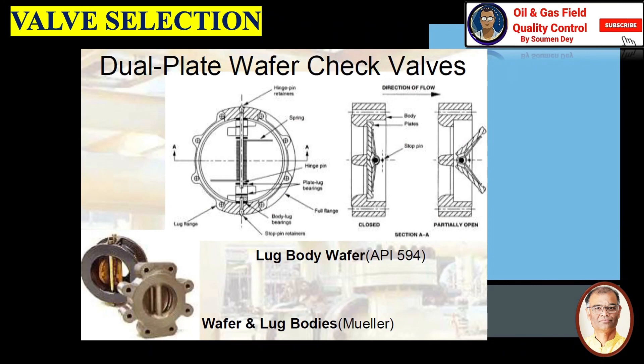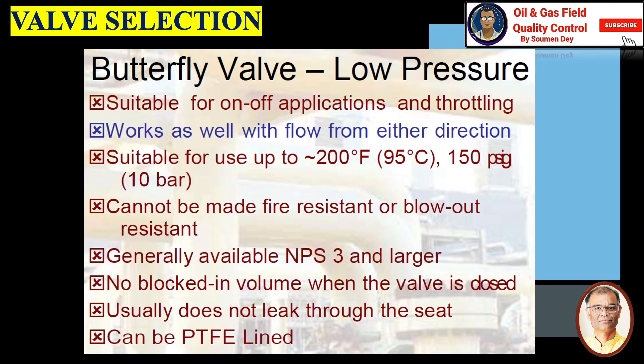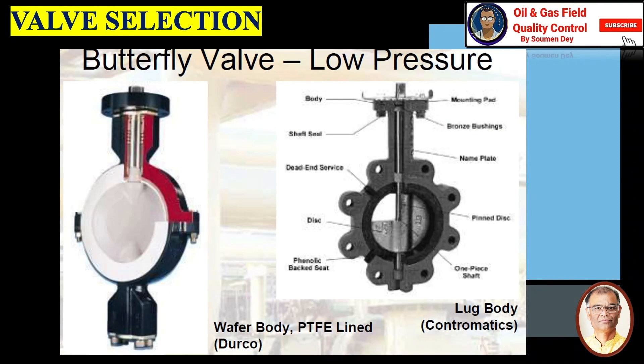Dual plate wafer check valves have excellent non-slam properties. Butterfly valve (low pressure): suitable for on and off application and throttling, works with flow from each direction, suitable for use up to 200°F (95°C) and 150 psig pressure. Cannot be made fire resistant or blowout resistant. Generally available NPS 3 and larger. No blocked-in volume when valve is closed, usually does not leak through the seat. Can be PTFE-lined.